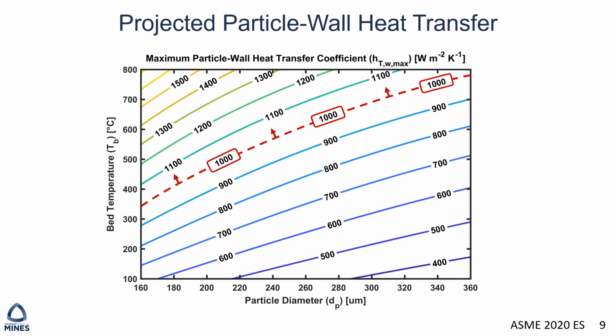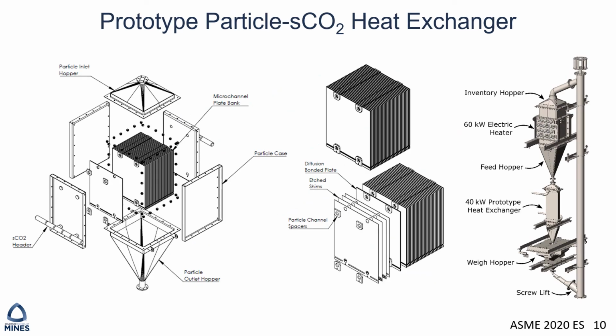Moreover, decreasing particle size is expected to provide significant gains in heat transfer, with heat transfer coefficients increasing with 160 micron particles by almost 40%. These data are being used to inform the design of a prototype 40 kilowatt particle SCO2 heat exchanger that is to be fabricated and tested at Sandia's SCO2 flow loop.